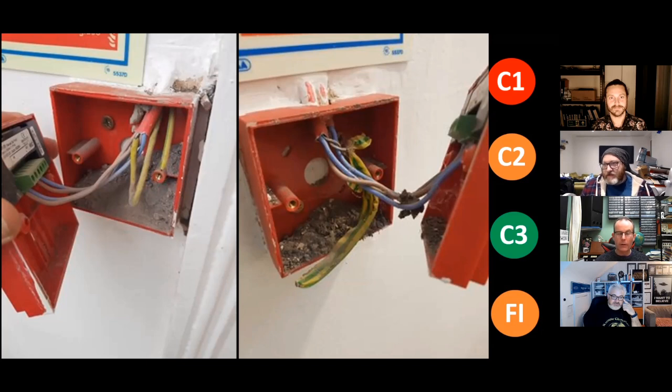Just for the completeness of those listening, Paul, you mentioned the screws. What's your beef? I was taught not to use countersunk screws unless you're on wood. Use a panhead, to get a proper cross-sectional area across it, with penny washers if you need to spread the load. Is that suggesting there's some mechanical strain on the enclosure? Yeah, because a countersunk is designed for wood, and when it goes into that plastic, all it's going to do is warp the plastic, so you've got less point of contact on the screw, so it's easier to rip off, which is just wrong.